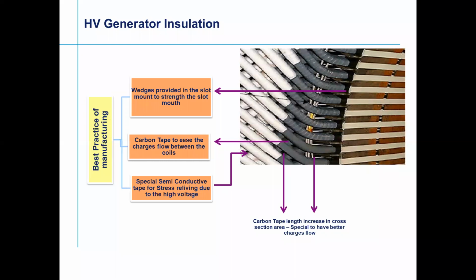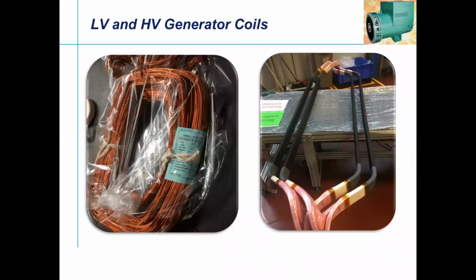That's the reason I thought of sharing this information. So you can see, maybe the team can have a guess which is LV and HV. I think I have two to three seconds. So this is the HV generator coils. This is how the insulation of the winding formed coil looks. On the right hand side, you can see how the HV coil of the generator looks. Predominantly, as discussed, there is a carbon tape, and over that there is a different one. This is fitted into the winding. This is how it looks.